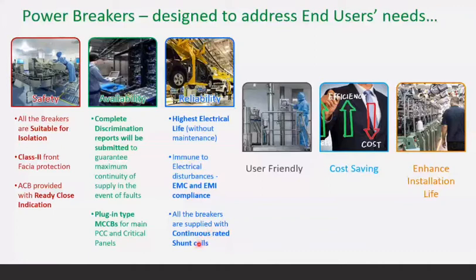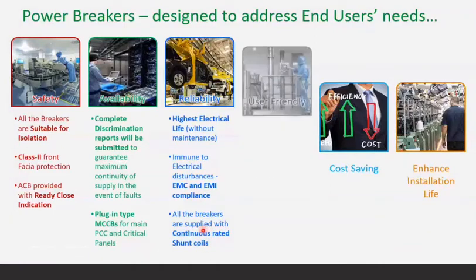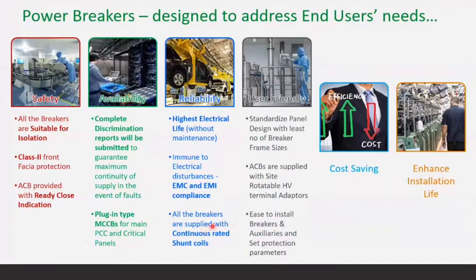Coming to the next point, all our breakers are supplied with a continuous rated shunt coil. This is also very important. In case you don't have a continuous rated shunt coil, and if you give a supply by mistake, there is a chance that it will go off.